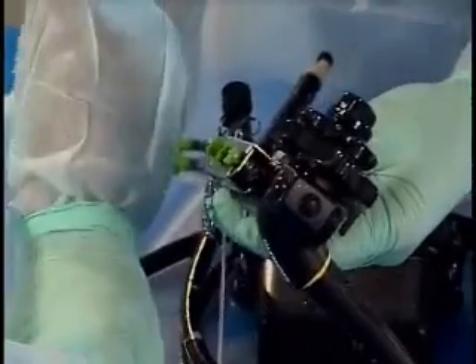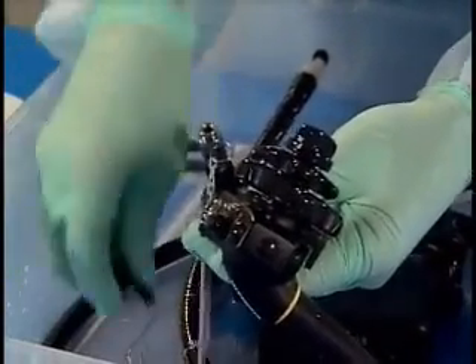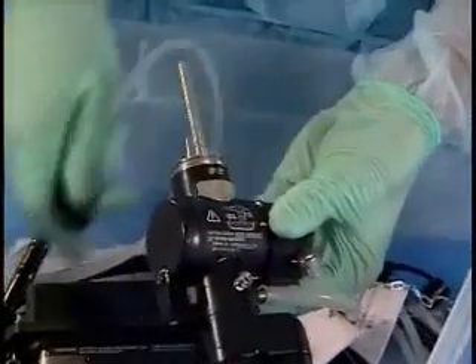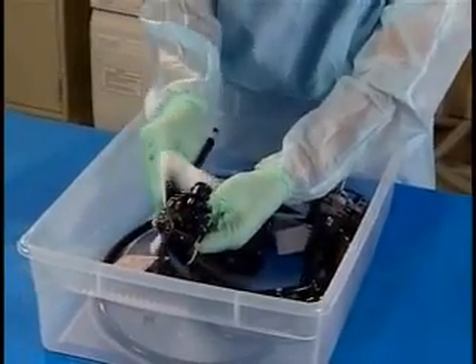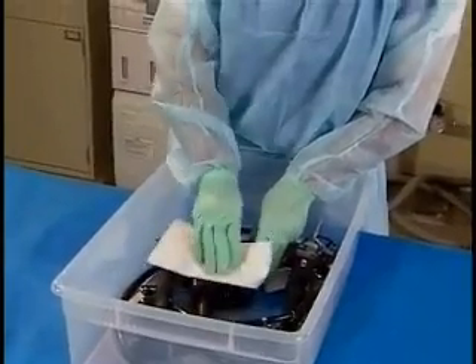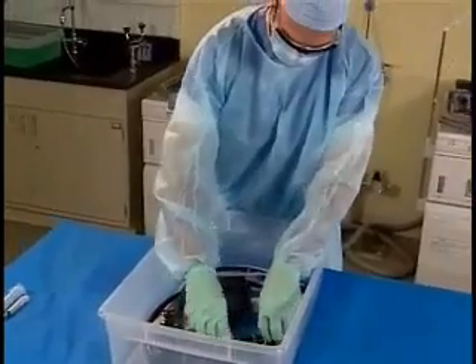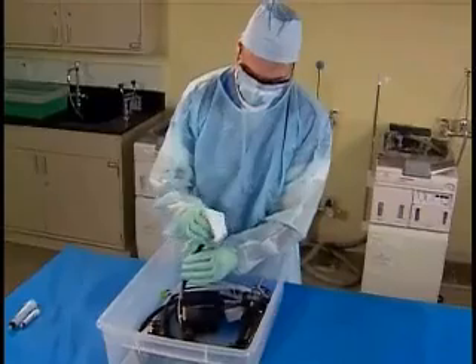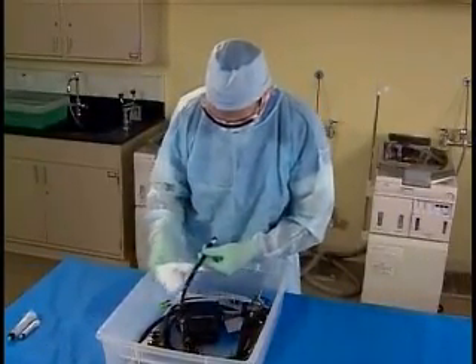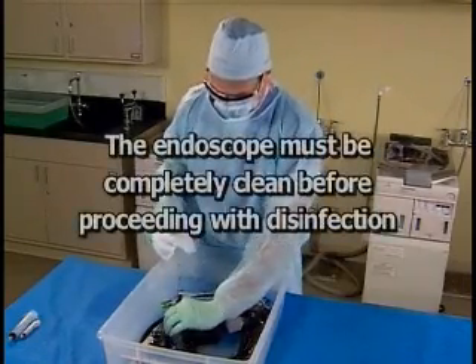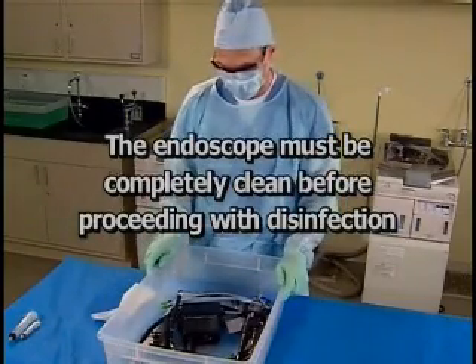Detach the washing tube, channel plug, cleaning and injection tubes. Now, use a lint-free cloth to dry the external surfaces of the endoscope and all cleaning accessories. Visually inspect the endoscope and cleaning accessories. If any debris remains, the manual cleaning process must be repeated. The endoscope must be completely clean before proceeding with disinfection.